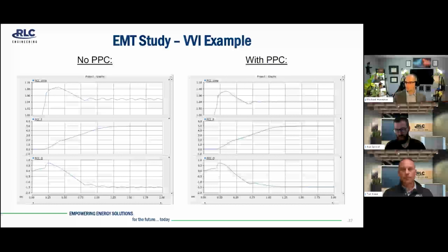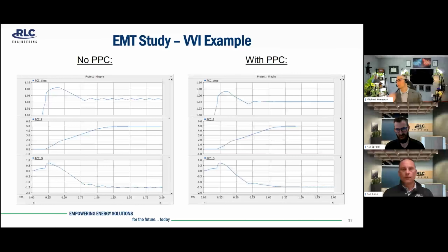One thing I'd quickly note regarding PPCs is we have had experiences in the field where PPCs don't necessarily operate correctly and can result in their own control oscillations rather than fixing the issue when applied to projects with low POI short circuit strength. We've actually seen the same with inverters, so it's always important to ensure that your design has proper capabilities for the proposed application, as with anything else.